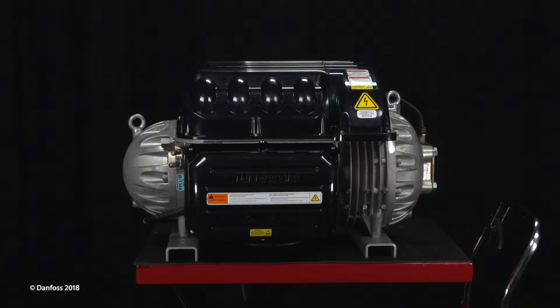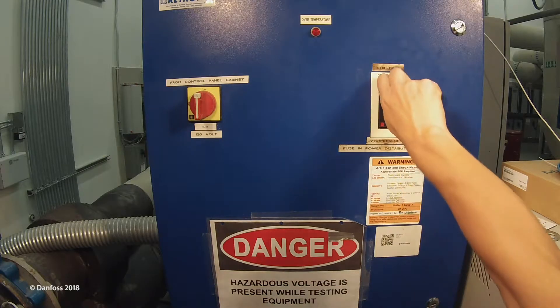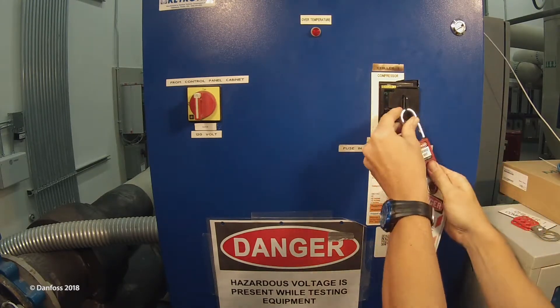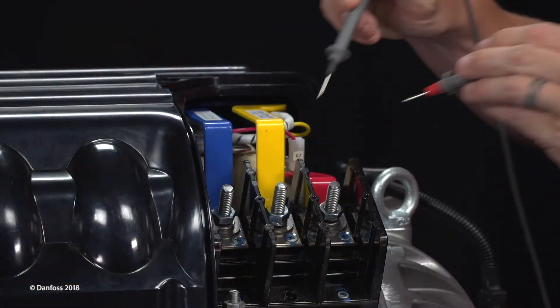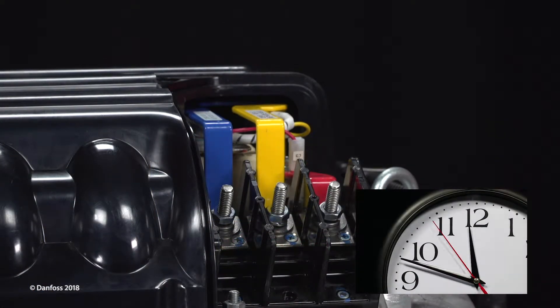Before performing any service on a Danfoss Turbocor compressor, electrical power must be isolated. Turn off the mains input power to the compressor and lock out tag out the mains disconnect. Confirm that the AC voltage is isolated. Wait at least 20 minutes for the DC bus capacitors to discharge.